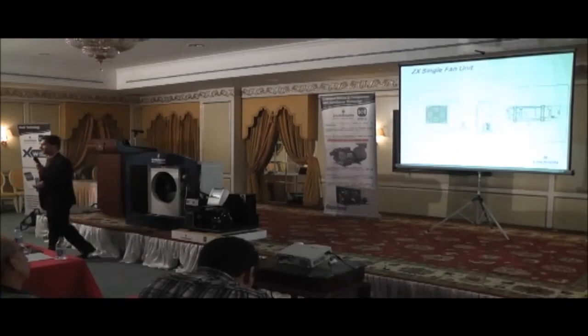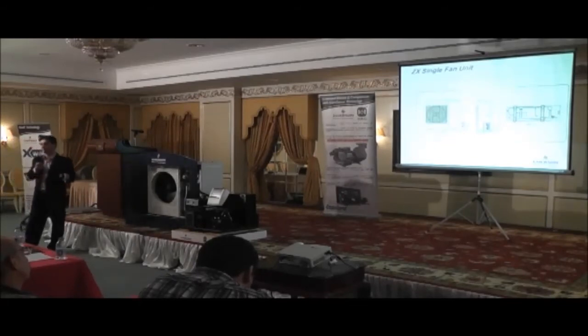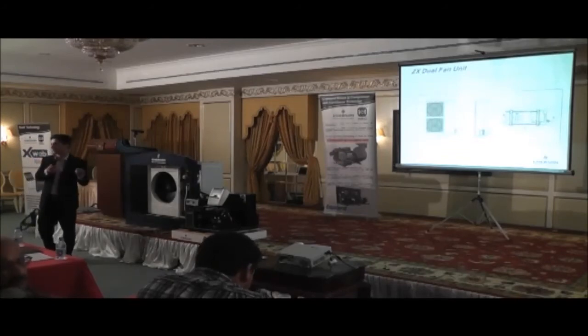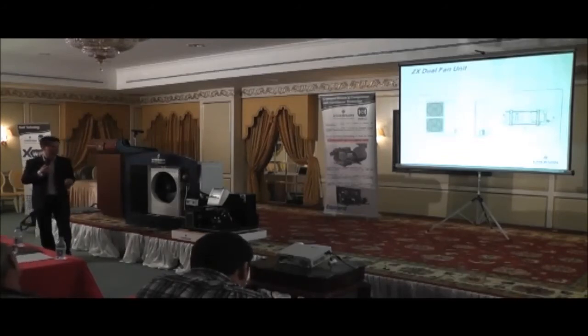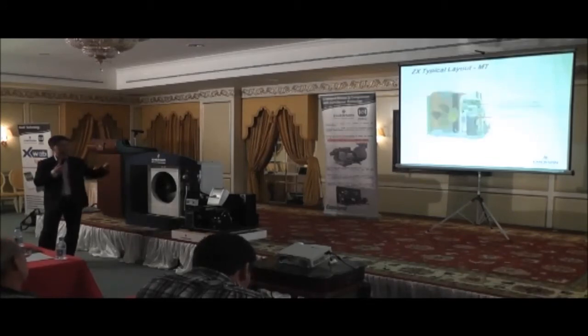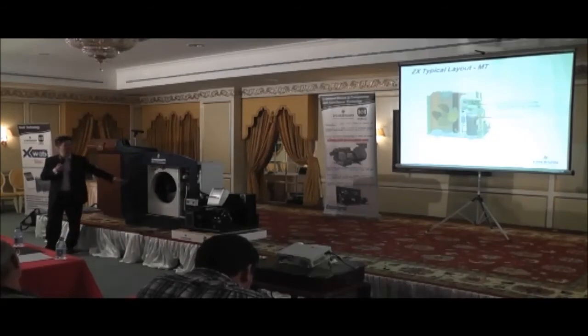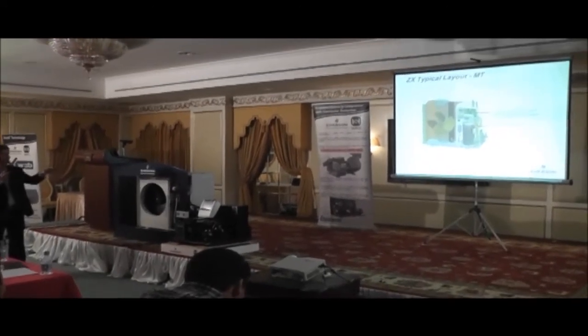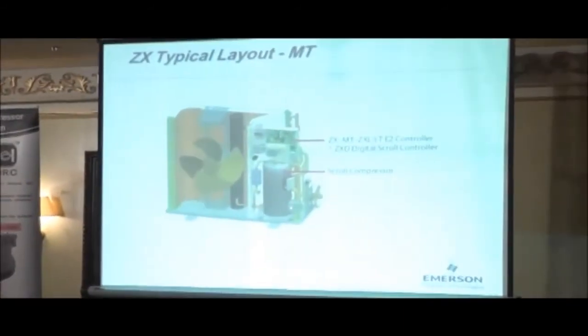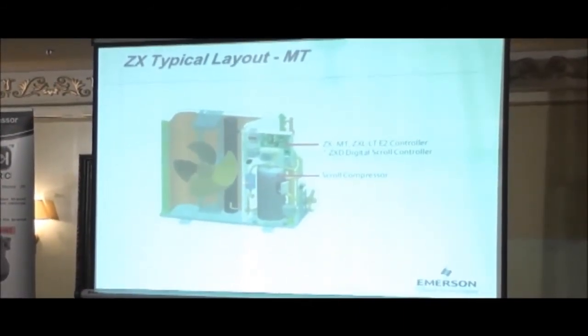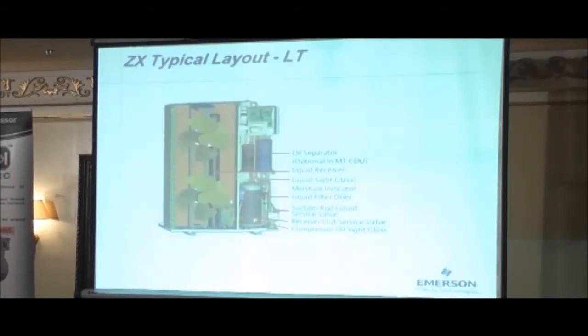These are the dimensions, it's pretty compact. The footprint for the single and dual fan is exactly the same. We just extend the height to accommodate the second fan. So it makes it easier for site installation by standardizing the spacing of your brackets. So this is a typical layout. We've got an example right here. Basically we have the condenser compartment, the receiver, the fan. In this section here we have the compressor with the liquid line sight glass, and then the electrical components around the top section. On the LT, exactly the same, except that we have an oil separator and we have the accumulator.